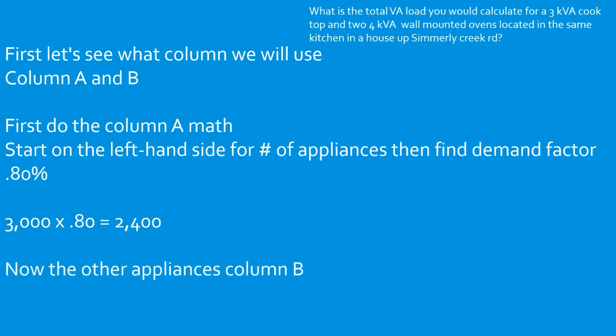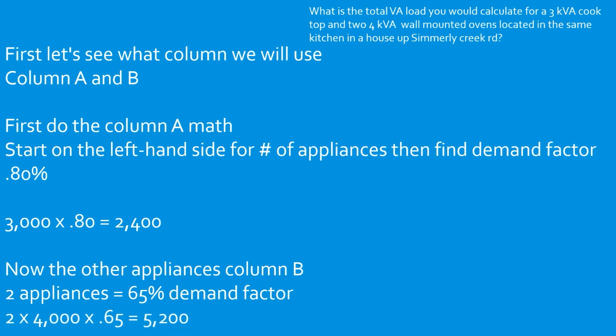Now let's do our other appliances. They fall into column B. So we start on the left-hand side for our number of appliances. We come over and fall under column B. We have 2 appliances, and we're going to find that we have a 0.65 demand factor. Now all we do is do the math. So we take our 2 ranges that fell in column B, multiply that by 4,000 because each one is rated at 4,000, and then we multiply that by 0.65.